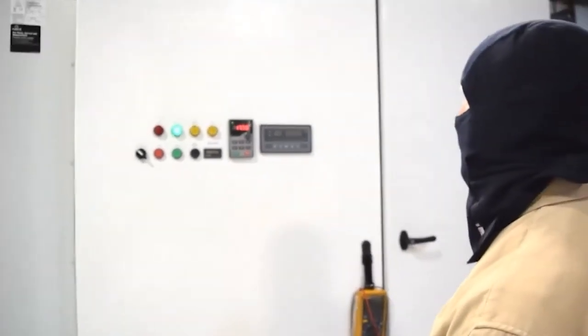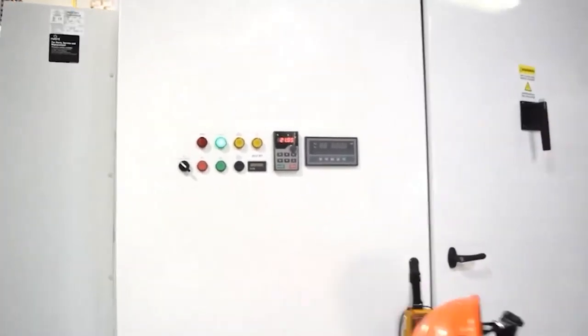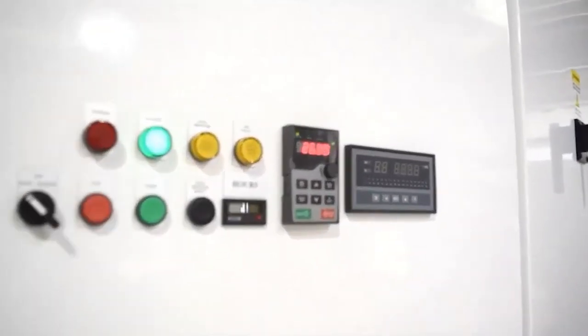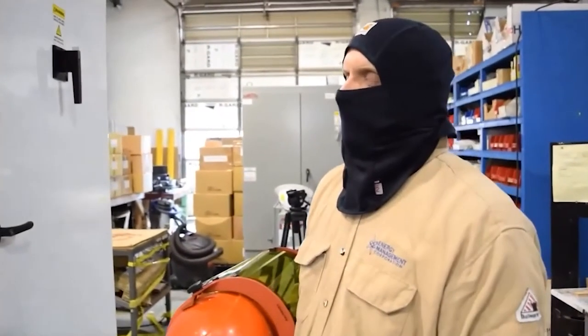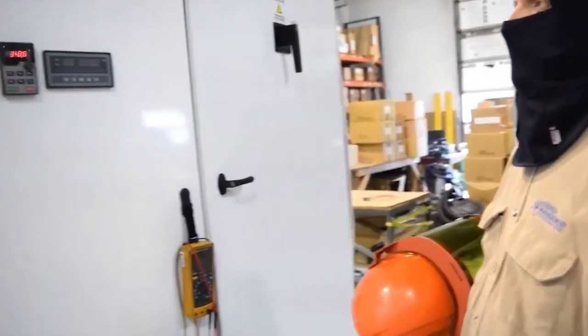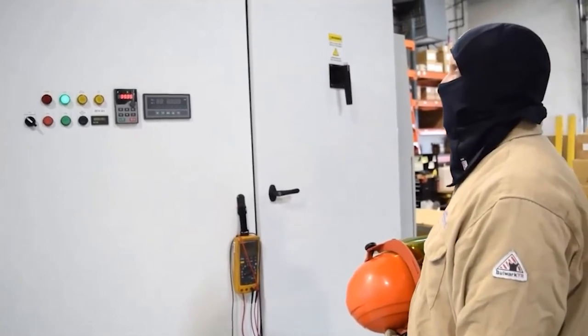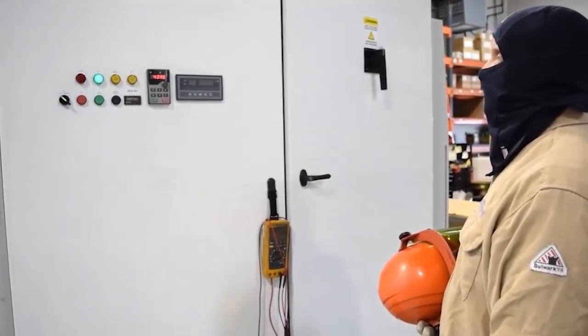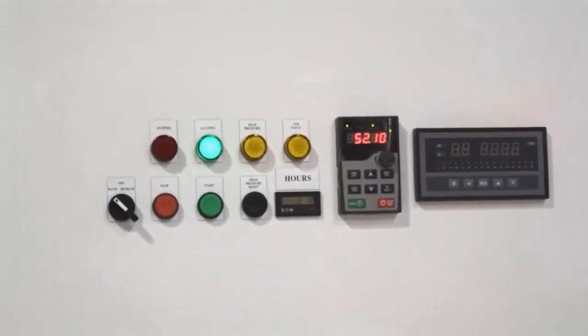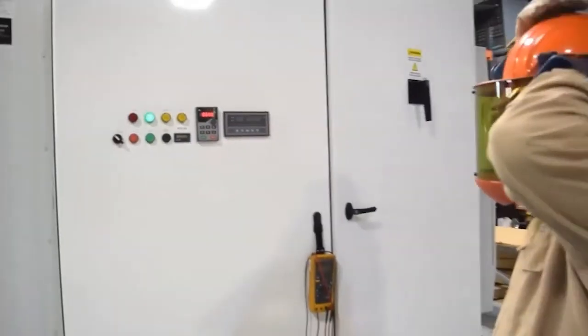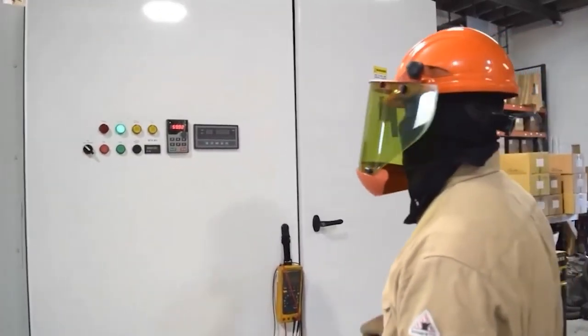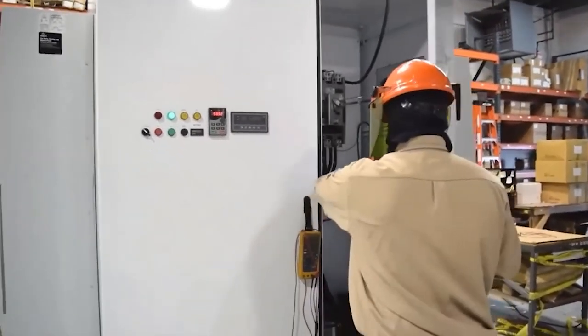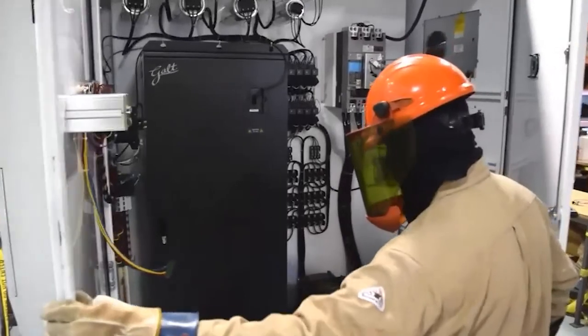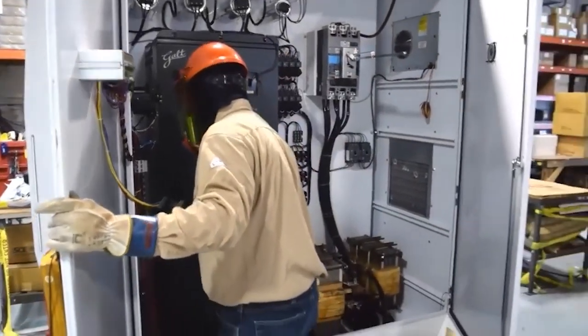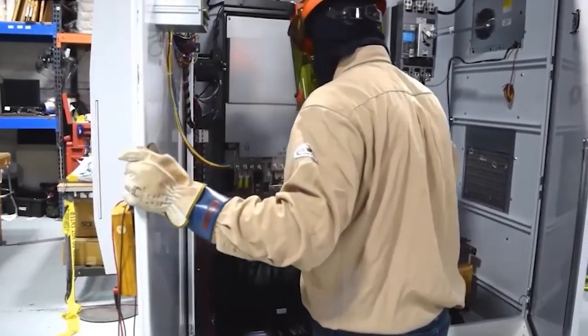Now, you want to make sure that your frequency is stable. If you're trying to measure your voltage on the output of a drive while your frequency is moving up and down, you're going to get readings that are moving up and down, which is going to be hard to determine if you have a problem with one of your transistors gating properly. Once you have your frequency stable, which means your voltage should be stable, you're going to measure your output terminals and you should get a real stable voltage. Usually you're within 1 volt of each other between A to B to C phasing. If you have much more of a variance than that, that's usually an indicator that something's not firing properly in the output.